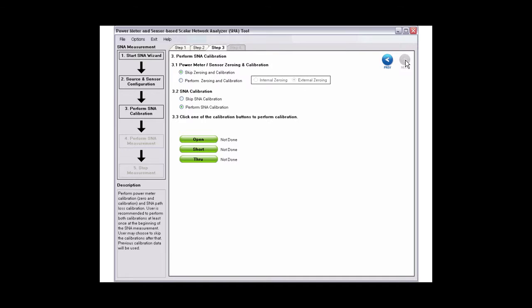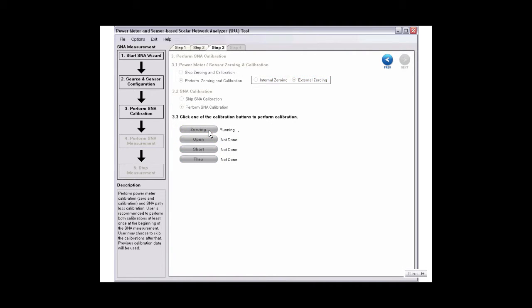Before you perform SNA calibration, it is recommended that you perform zeroing and calibration for the power meter and sensors. Click zeroing button to start power meter and sensor zeroing. Once done, the completed status will be shown.